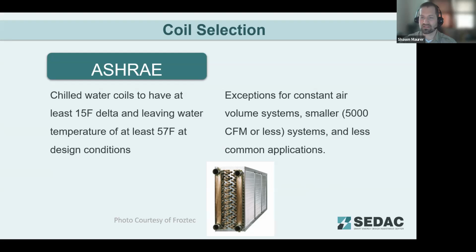Looking at coil selection, previously a 10-degree delta T was common practice for chilled water coils. ASHRAE is raising that design criteria to 15 degrees. Again, this is not included in the IECC. It's still working off that 10-degree original industry standard. This can reduce pumping required as coils can absorb more heat than they can with a 10-degree design. So you're increasing that temperature difference.